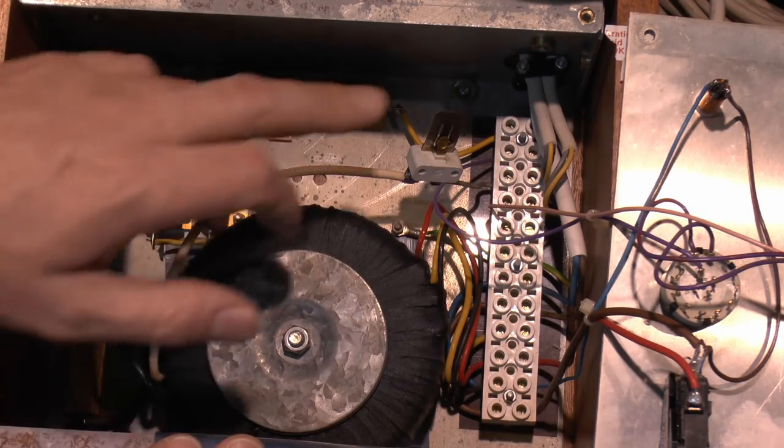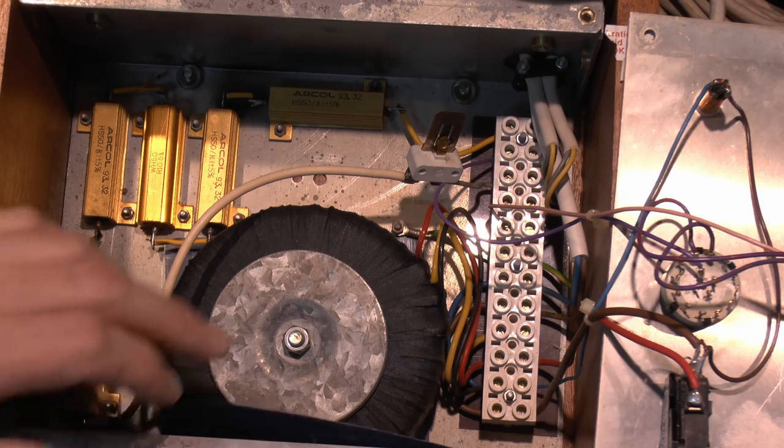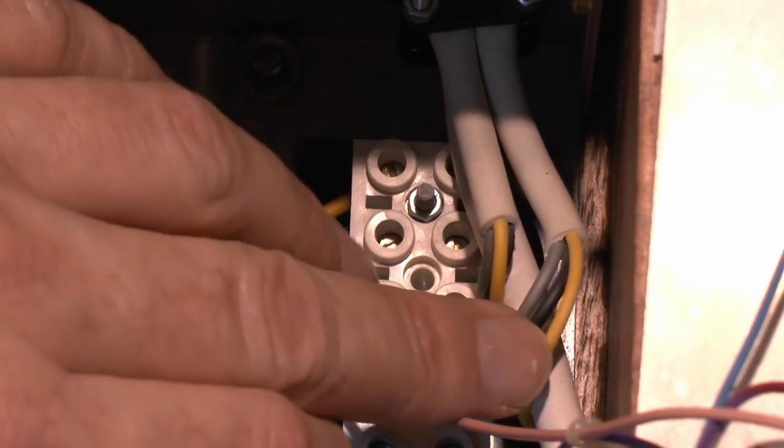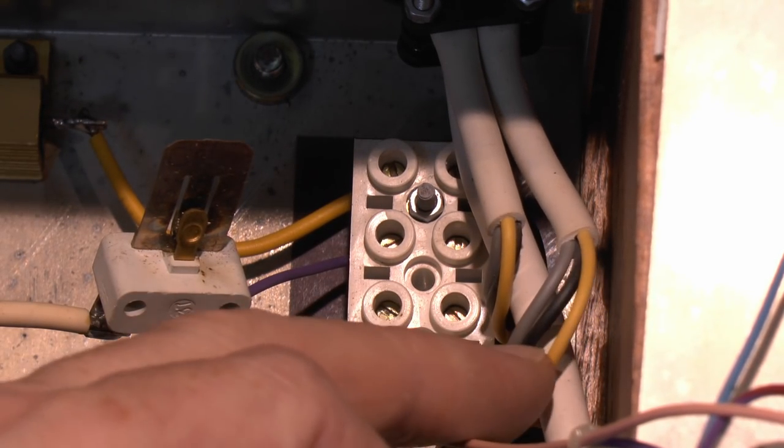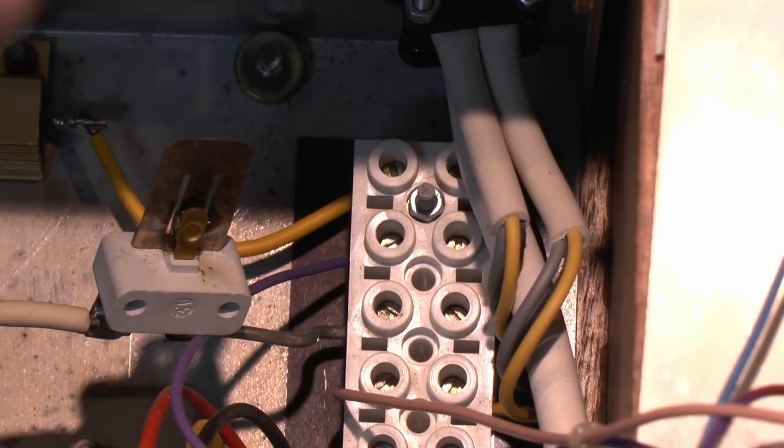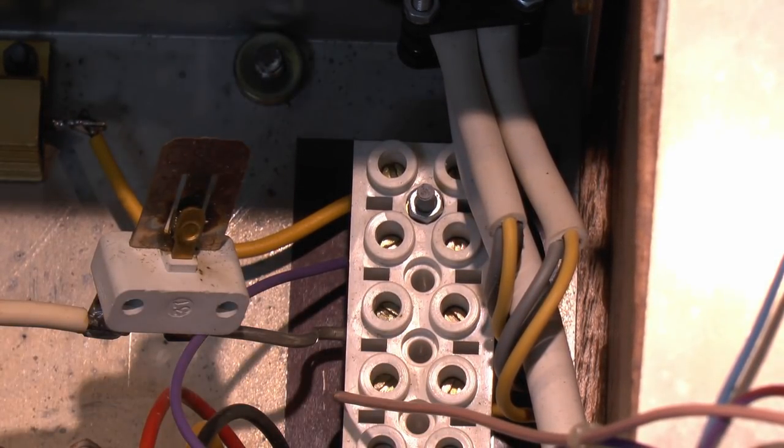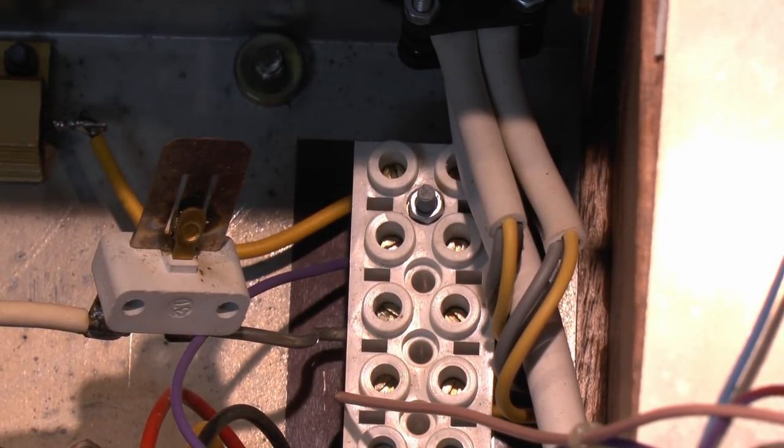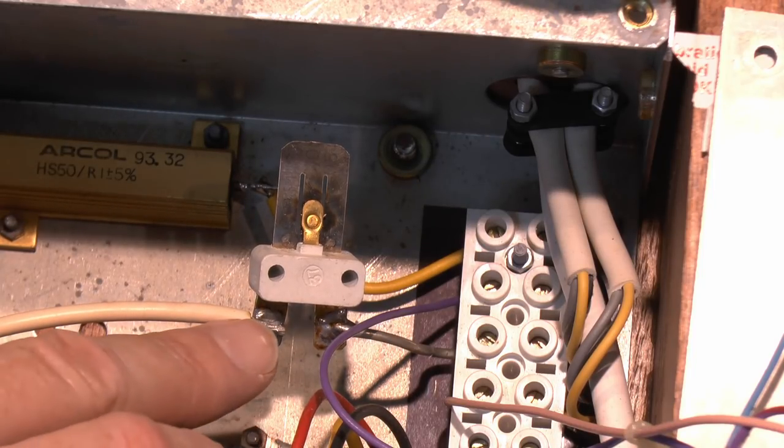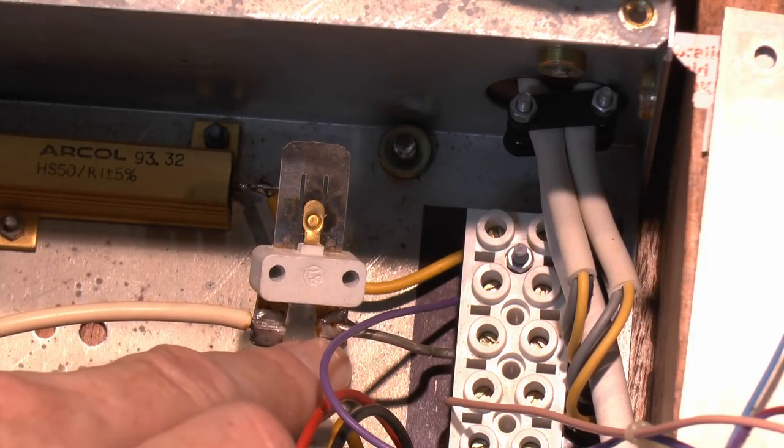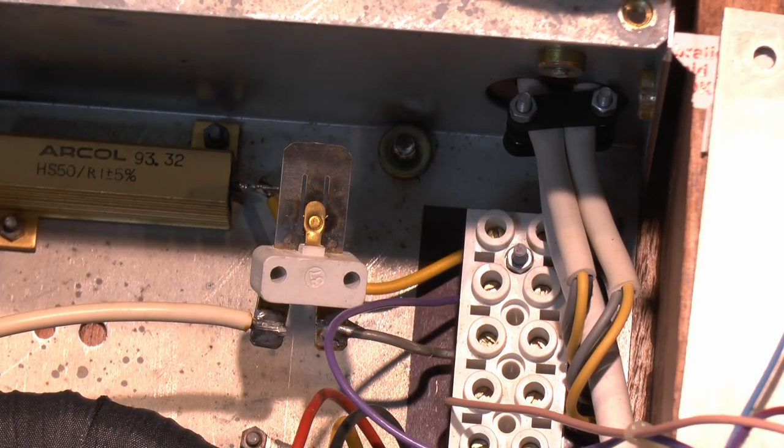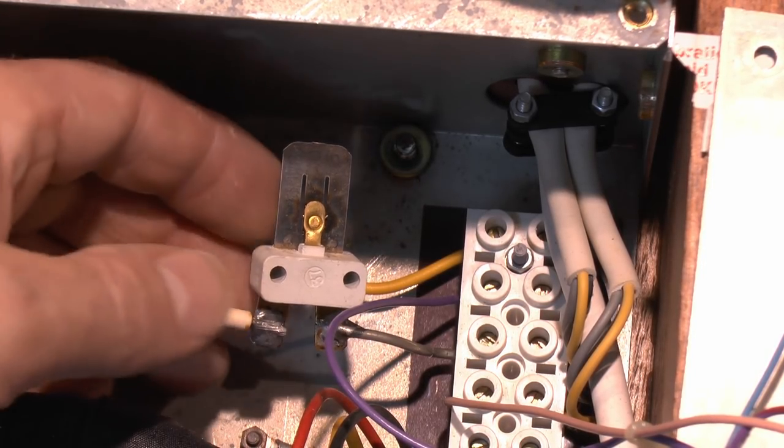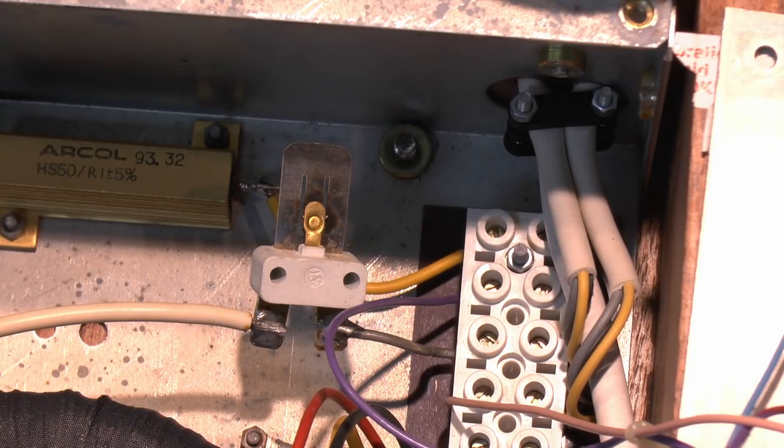Terminal strip over there, which just connects to the various other items. The switch on the front panel. And then we've got our three wires coming in here from the main supply and the two test leads. Now you can see the test leads here, it's got these multiple wires within. And again, that's how it's got the voltage and current lines there. We've actually got three there, the grey, black and yellow. That's certainly a custom manufactured flex item. It's going down onto the board there. And our main supply coming in is the line neutral and the earth connection on that side. Here's the thermal cutout. So essentially the full current is going through this piece here, just the inside and outside connections there. And essentially when the current goes through this, this will heat up. And then as it bends, when it gets to a certain point, it will click over and break the circuit. And then once the circuit's broken, it will cool and then click back the other way. So just a safety device there to avoid someone holding the button down for too long or, for example, with a button jammed in the on position. That would cut it off after a short amount of time.